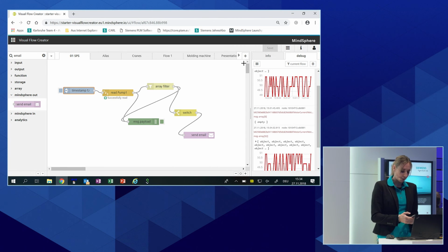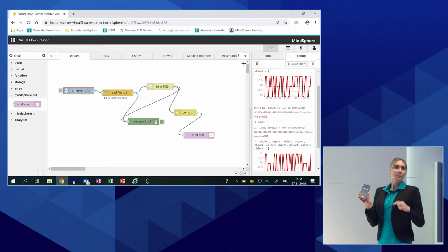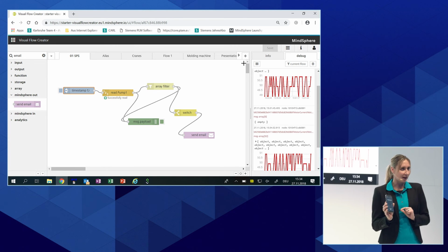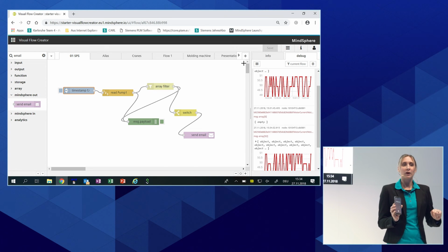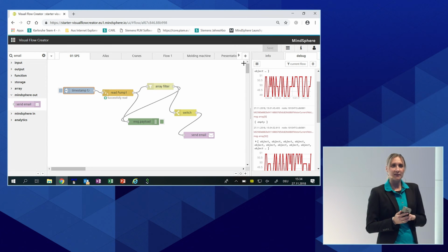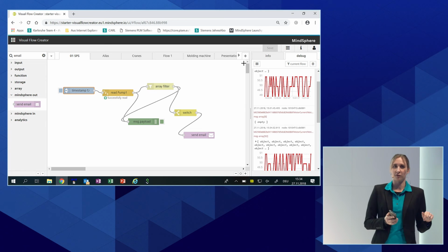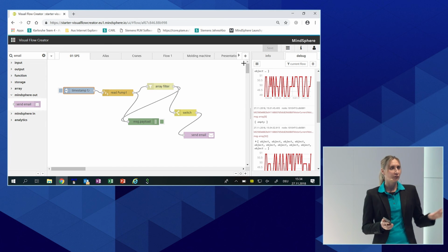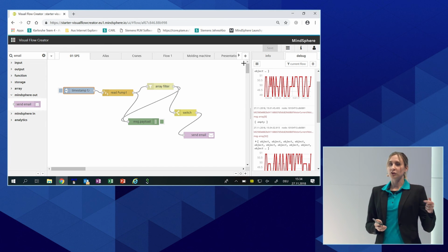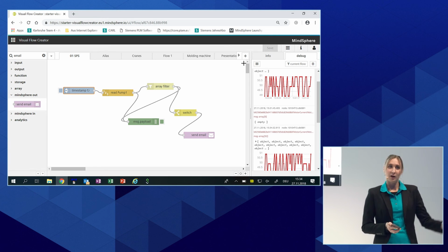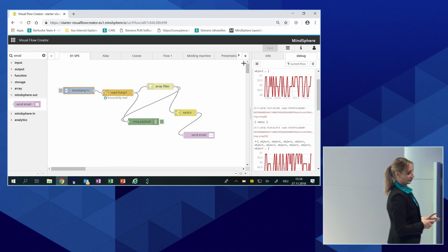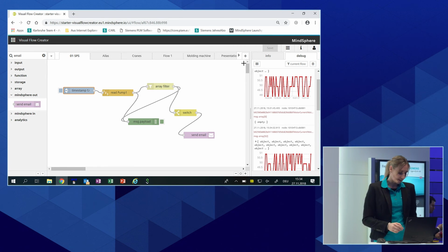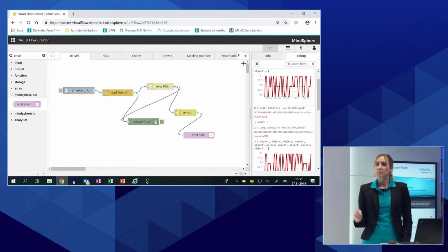And what I will do now, with my mobile phone, it's really live. I will simulate a dry run of the pump. The pump is located in Erlangen, and I can simulate this dry run. And if we have configured everything in the right way, then I should now get an email notification because the values go down. It just takes a few seconds because it has to be simulated.